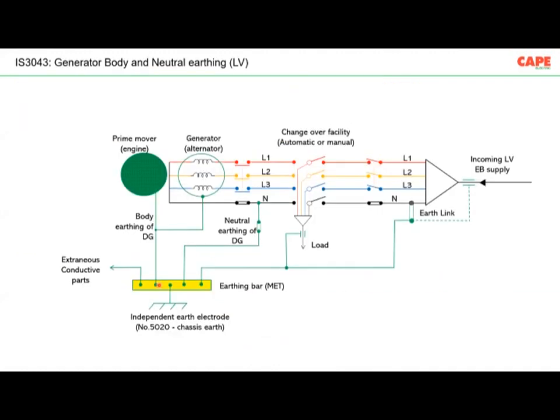How to make an earthing of your DG, for example: in IS 3043, pictures 38 to 41, you can find this picture. The only difference is I put it in a color combination, red, yellow, blue, neutral in black, and green is the earth wire. The DG body, engine and alternator body, is connected to an earth bus bar. Neutral of the DG is connected to the same bus bar. The incoming EB supply PE conductor is connected to the same bus bar.